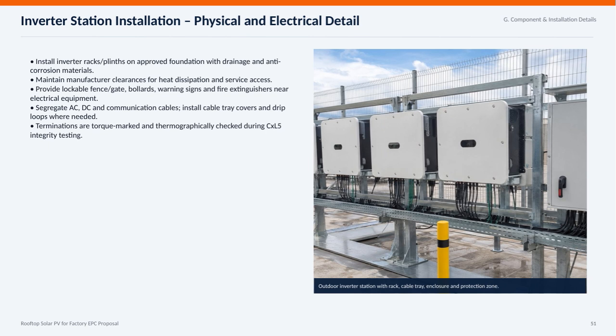For safety, we provide a lockable fence or gate, bollards, warning signs, and fire extinguishers near the electrical equipment. Additionally, cables are carefully segregated: AC, DC, and communication wires are separated, with cable trays covered and drip loops installed where necessary to protect against moisture. Finally, all terminations are torque marked and undergo thermographic checks during commissioning to verify their integrity.